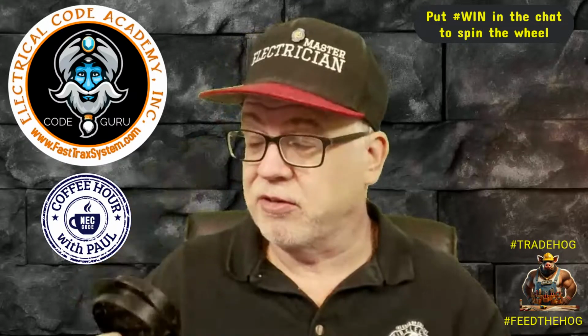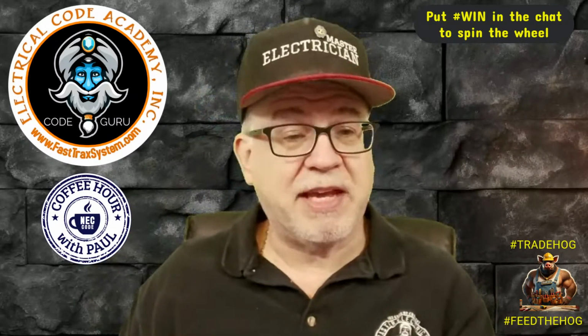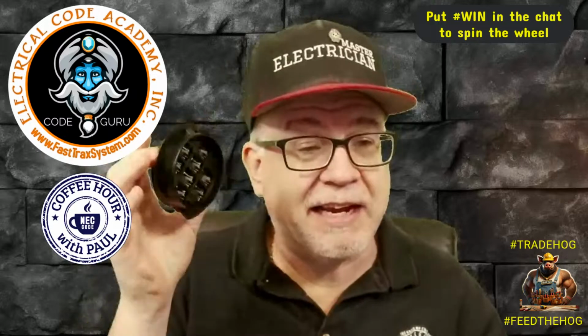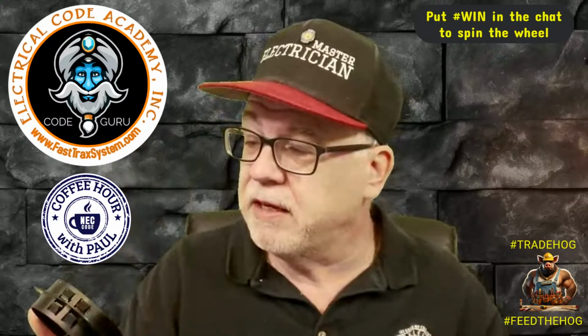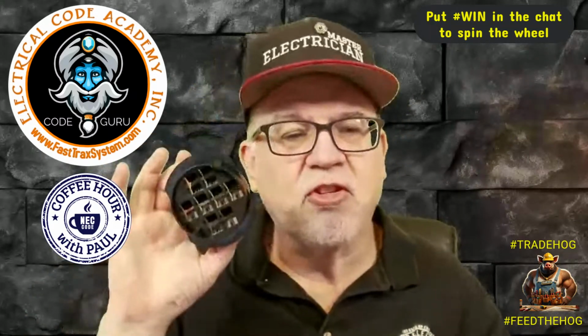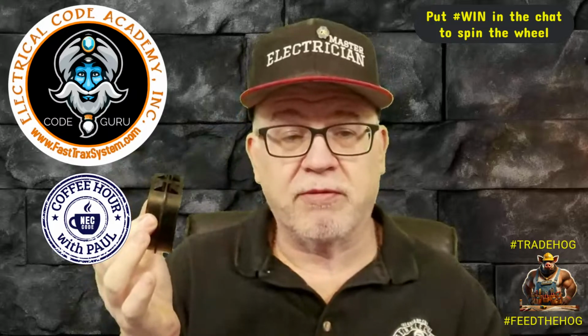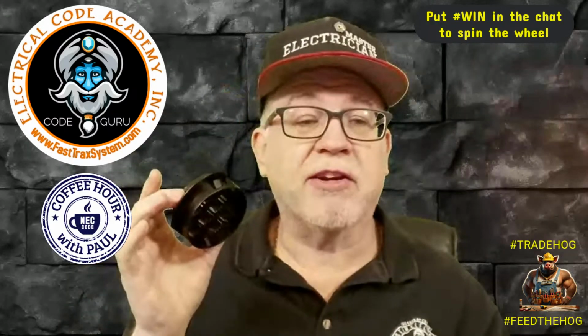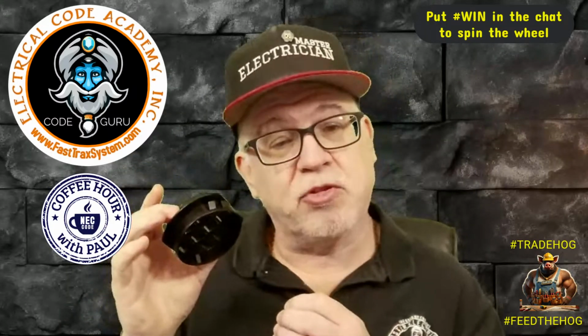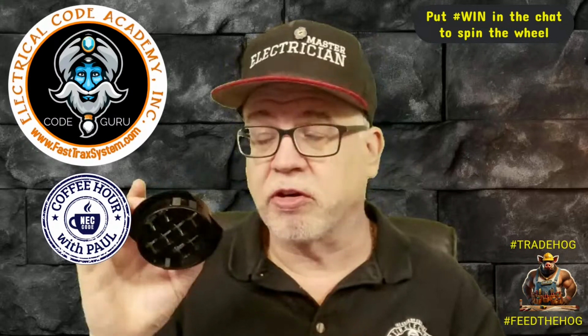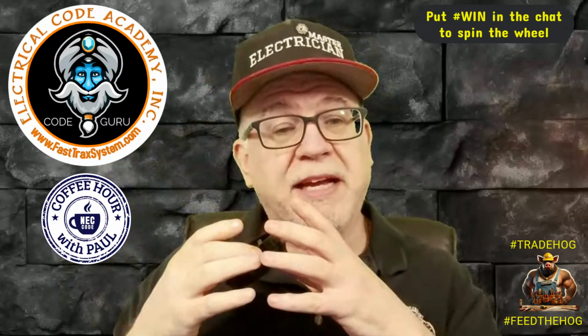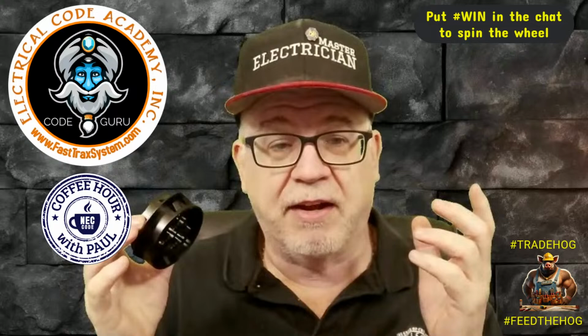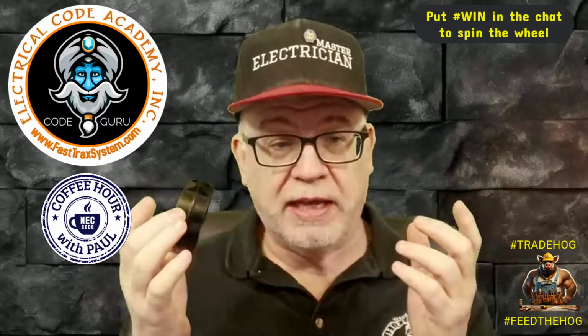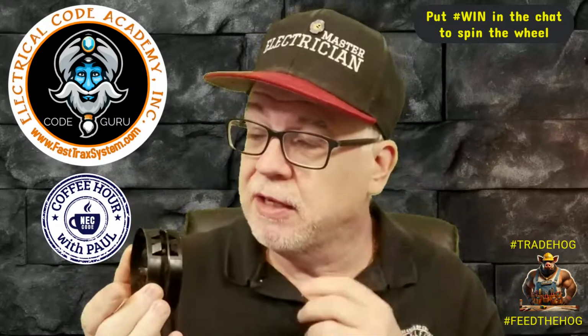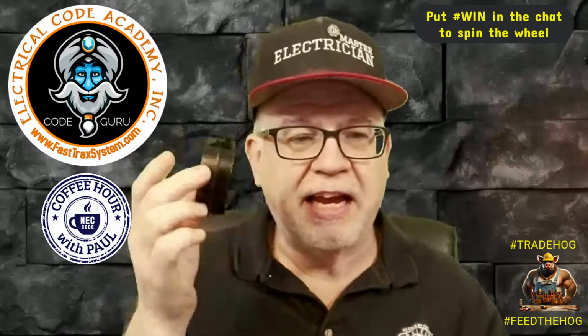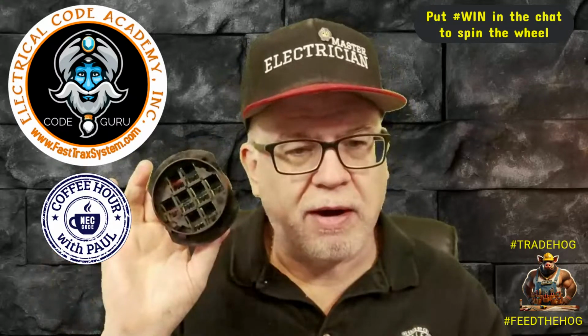I invent stuff all the time, different types of cables, but I didn't think about something like this. At the end of the day, this solves a violation that's very common, 312.5(C), where you're required to secure every cable to a cabinet or enclosure. Well, if you bring them all through one big knockout, that's not meeting the intent of the code, even though inspectors may let you do it, especially out there in Arizona, that's not compliant. So this guy came up with this thing, and it's called a wire waffle.